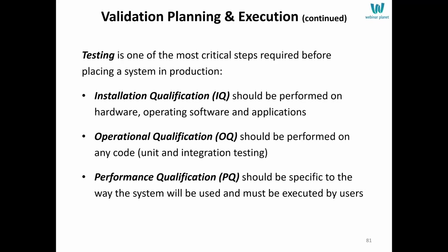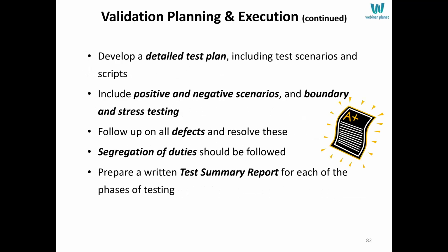Testing: IQ, OQ, and PQ. IQ for any component, OQ for the application software you're working on, and PQ for the application software if there's a specific way to execute it that might be different than how other clients of the vendor's products would do it. You want a detailed plan for all of this. Again, if more robust testing is needed, positive and negative scenarios, boundary and stress testing.